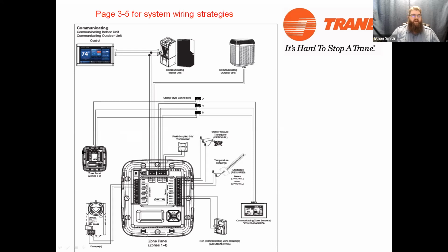We can tie in a second zone panel if you've got to go over and above 4 zones. We use power open, power closed dampers. We'll talk about those more in a second. We've got a variety of sensors. We have the non-communicating temperature thermistors, which we affectionately refer to as RATs, remote air temperature sensor.